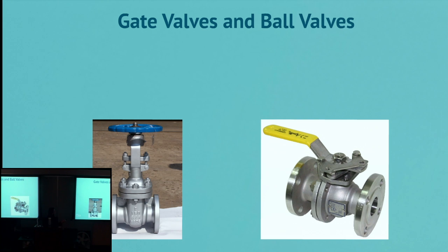And then this is a gate valve, and it usually comes with a wheel top. This ball valve has a handle, and both of these valves have to be in valve boxes. And if you do have a ball valve with a handle like this, you need a larger valve box than what you would need if the ball valve has a handle like this. You can specify the ball valve with a wheel handle. Now, out in the field, you can still look at these items when you're doing water coverage tests. You don't necessarily have to be there during installation.